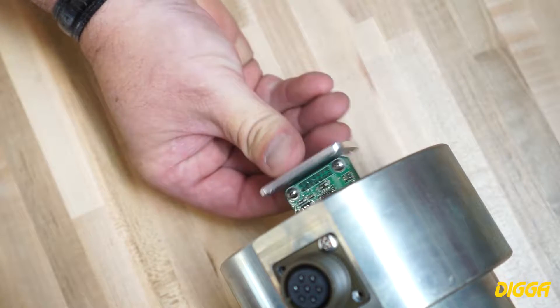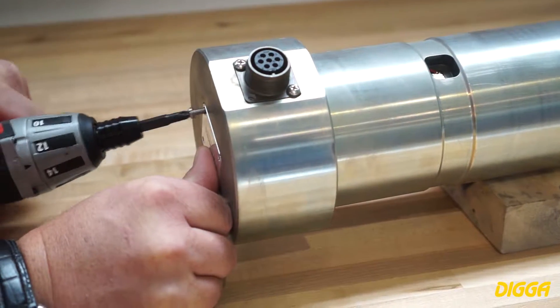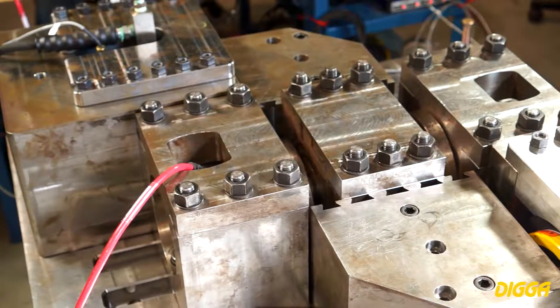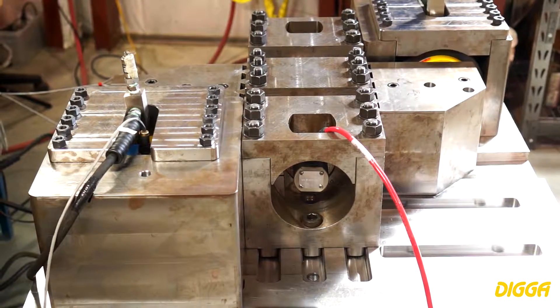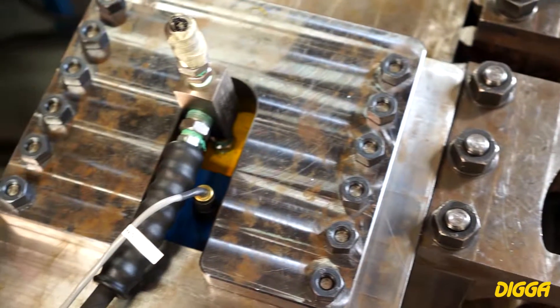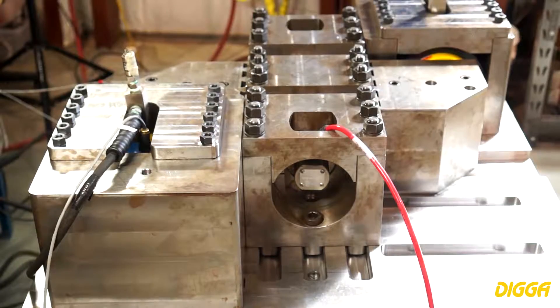The CPU is inserted in the pin head of the Torque Logic pin and is then filled to completely seal the electronics. All Torque Logic pins are calibrated on a custom engineered test bed capable of 400,000 ft-lbs or 550 kNm of torque, while simultaneously putting up to 50,000 ft-lbs or over 65,000 Nm of perpendicular force to prove no effect on torque.